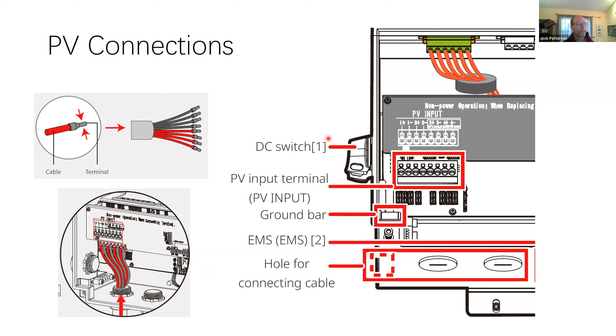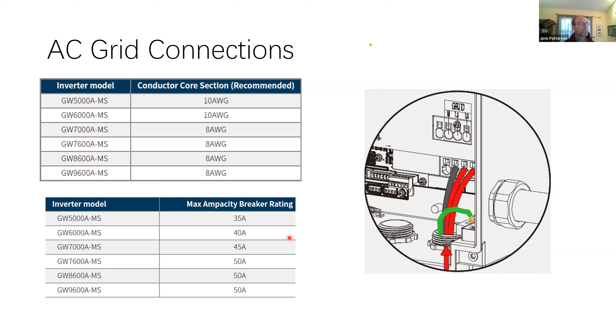The AC side, you'll consider using—you can use 8 or 10 gauge aluminum, copper is preferred—and then here are your breaker ratings for those different inverters.